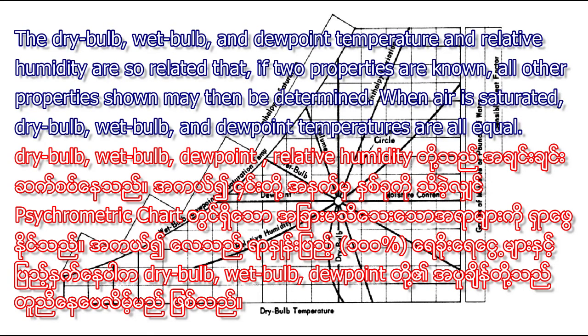The dry-bulb, wet-bulb, and dew-point temperatures and relative humidity are so related that if any two properties are known, all other properties may then be determined. When air is saturated, dry-bulb, wet-bulb, and dew-point temperatures are all equal.